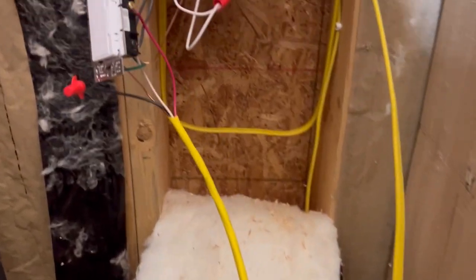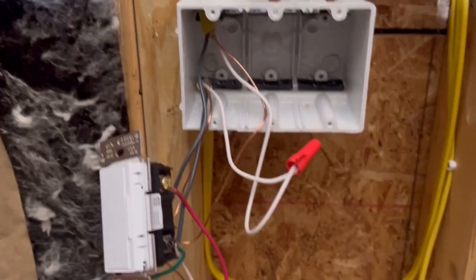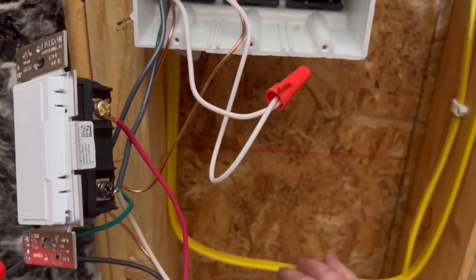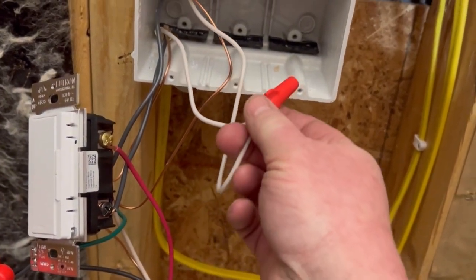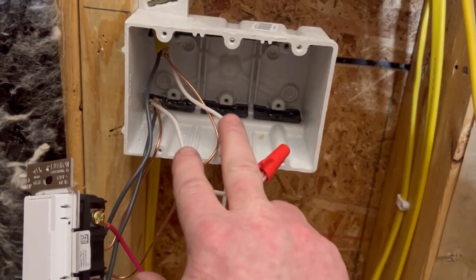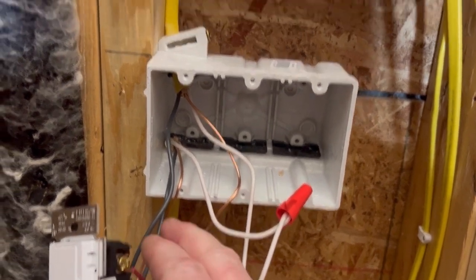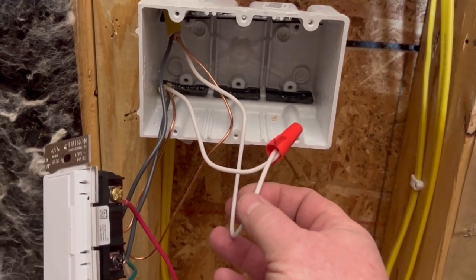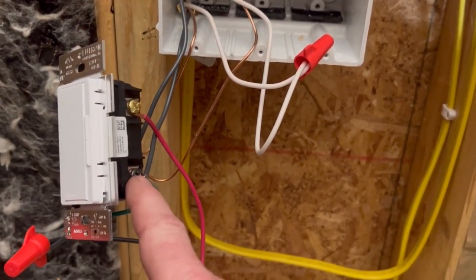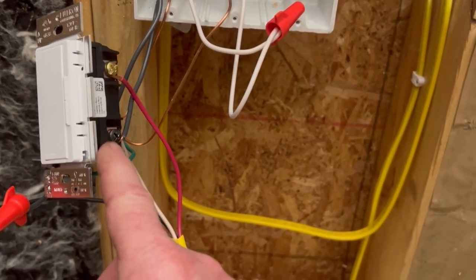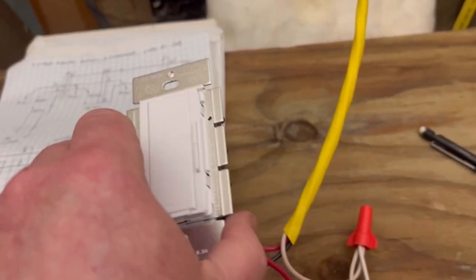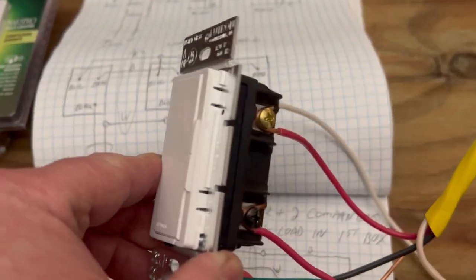So basically you just follow the diagram. Notice that this is my 12-2, this is my power coming in, and the neutrals get tied together. This is the power coming in, this is the 12-2 that goes up to the lights, so those neutrals get tied together. The power goes to the black screw.